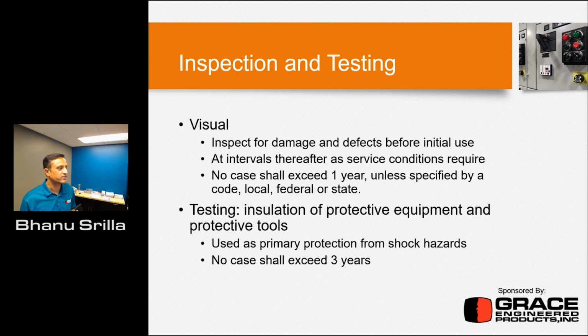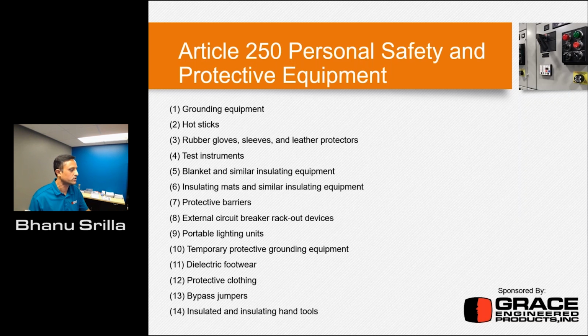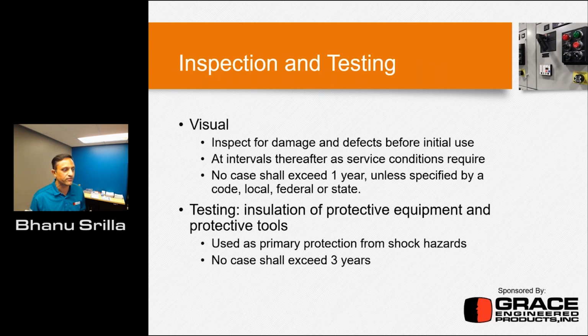Okay. So inspection testing. If you take these 14 items that I showed here, you need to have the visual inspection, inspecting for damage or defect before initial use. So whenever you put this in service for the first time, you need to visually inspect it. And at intervals thereafter, you need to make sure the service conditions are maintained. So the max, they say, is basically 1 year. No case shall exceed 1 year unless specified by code or a local authority or a federal or a state requirement. So you can't alter this unless otherwise there is a change defined by these regulatory bodies. Okay. So testing, insulation of the protective equipment and protective tools used as a primary protection from shock has to be tested. No case shall exceed 3 years. Once in 3 years, you have to make sure that your things are tested.